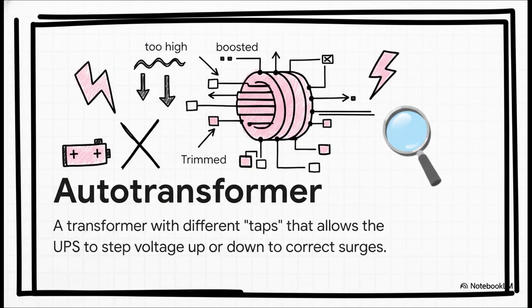Those extra wires are basically different connection points, or taps, set at different places on the transformer's coil. The UPS's main brain is always measuring the voltage coming in from the wall. If it's too low, a brownout where the lights dim, it uses little clicking relays to switch to a tap that boosts the voltage back up.